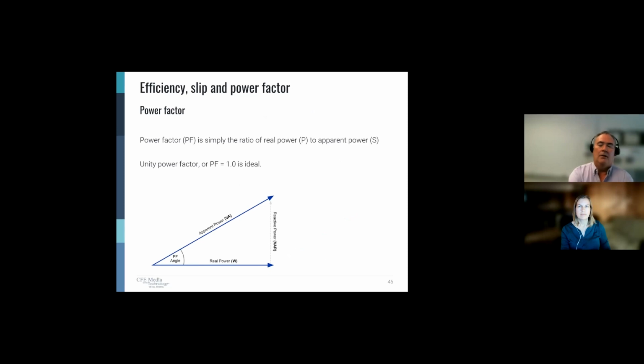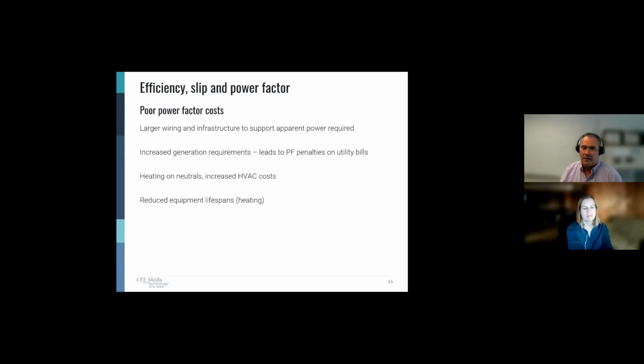Power factor is simply the ratio of the real power to the apparent power. Unity power factor, or a power factor of 1.0, would be ideal, because that would mean the real power and the apparent power were the same, and we're not losing anything through reactive power, sometimes referred to as VARs or kVARs, which stands for volt-amps reactive. Why do we care? Again, poor power factor has costs. If we have to create a larger infrastructure for larger apparent power because our power factor is poor, we incur those costs: larger switchgear, larger wire, larger connectors.